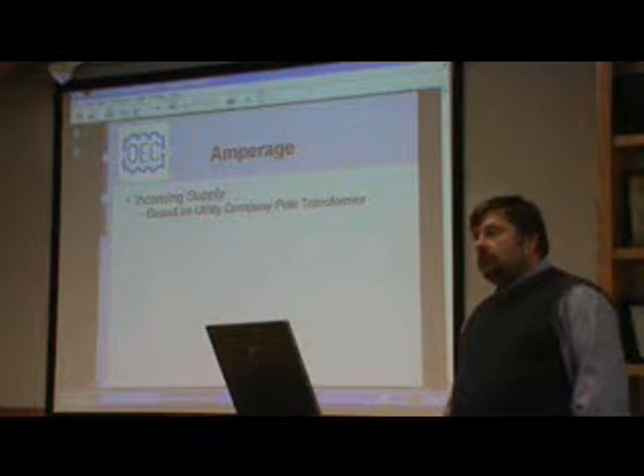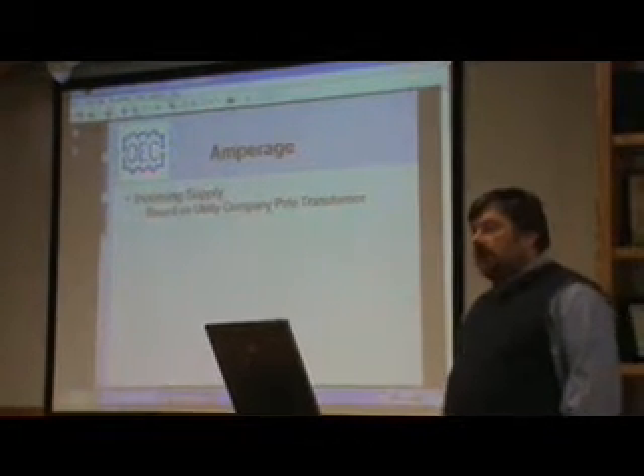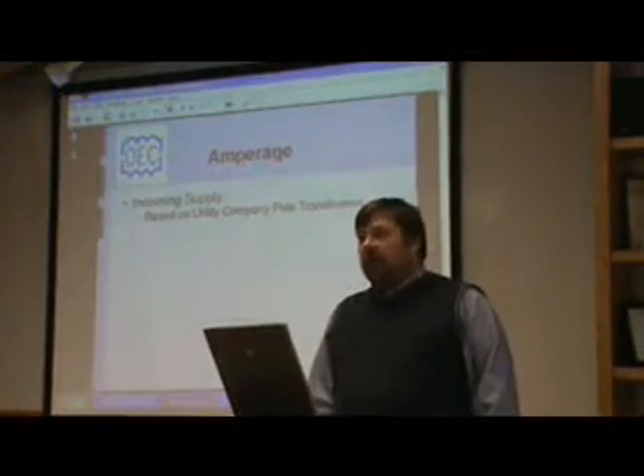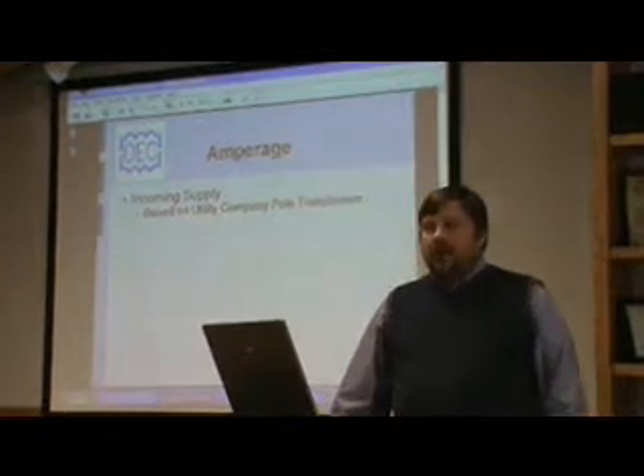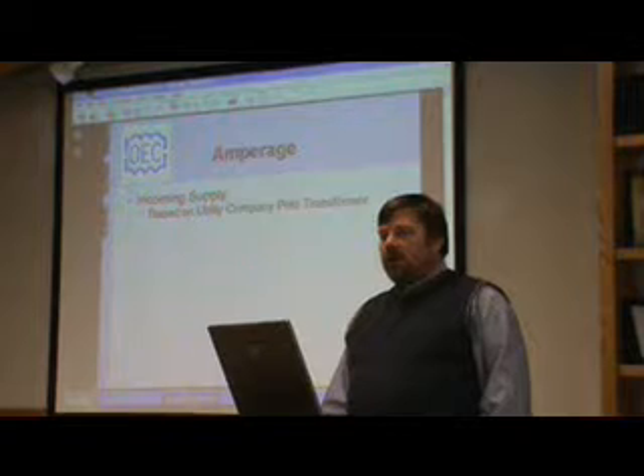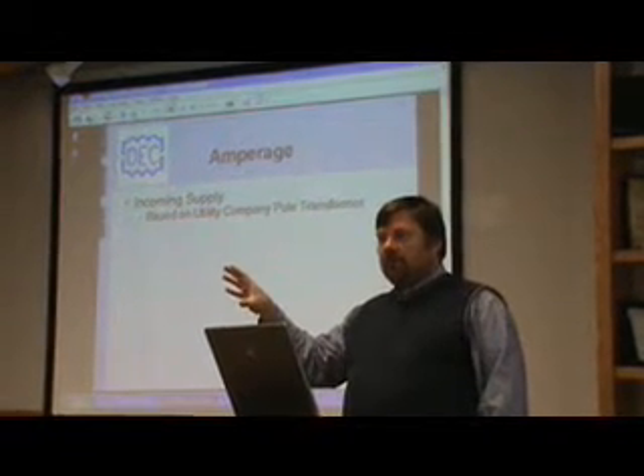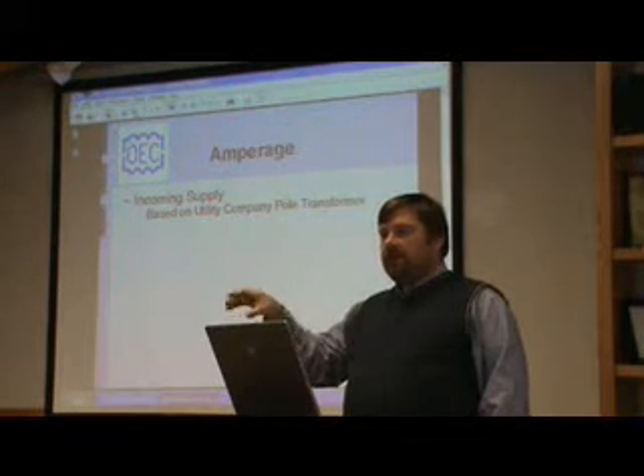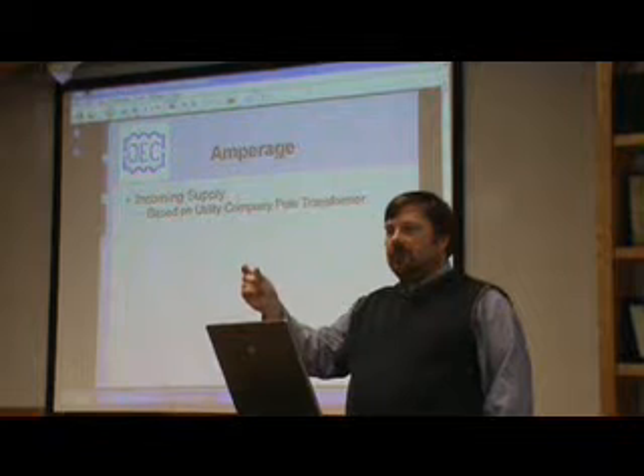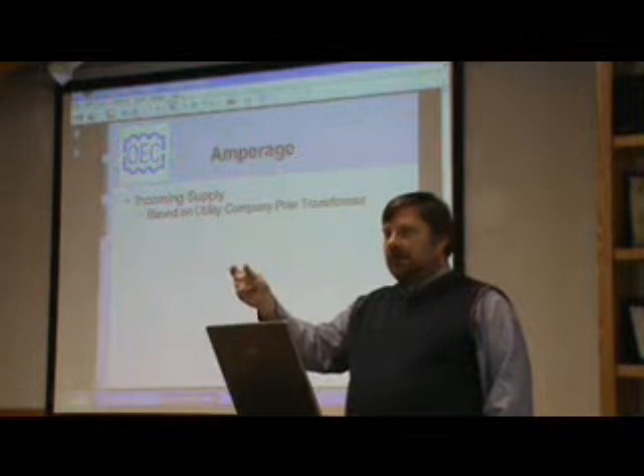Are you saying to make a note of that when we go out on something that has a diesel generator or a gas generator? Is that something we should look at? Yeah, if you're having problems where you're losing phase, we've had calls in for troubleshooting where people say, I get a phase monitor alarm every Tuesday at 2 o'clock. Well, the generator on that site would turn on and do its cycle for its exercising cycle, and they would get a phase problem because the generator frequency wasn't adjusted properly, and they only had 55 hertz of power, and the phase monitor saw that as a problem.